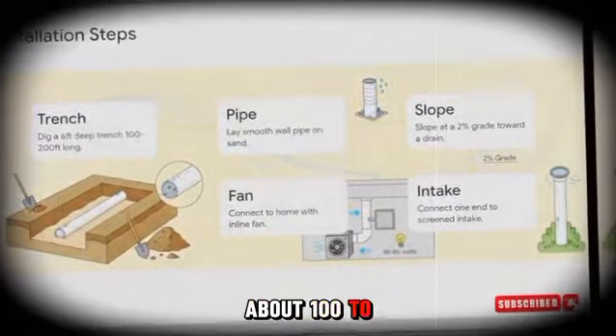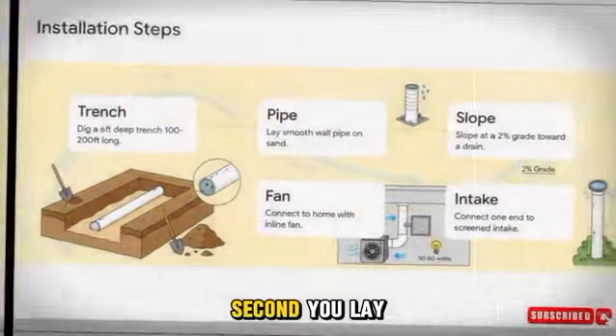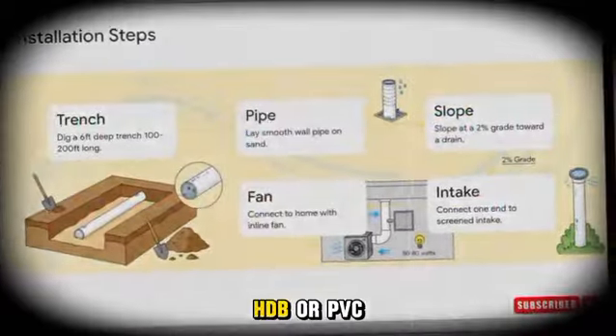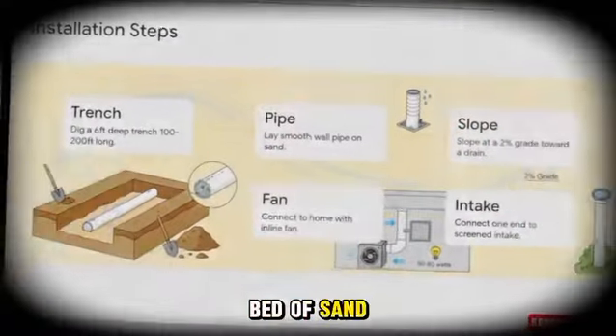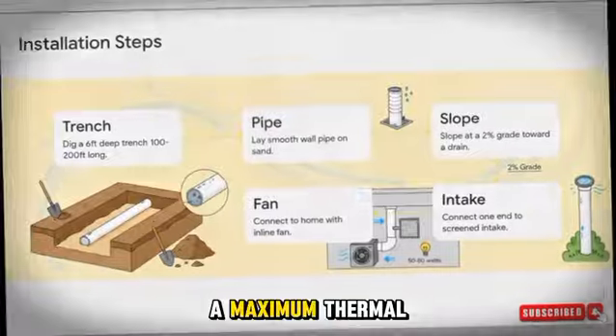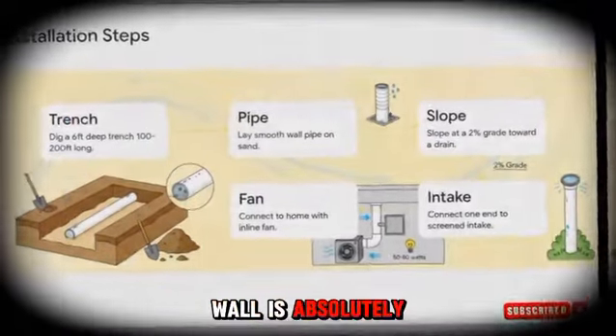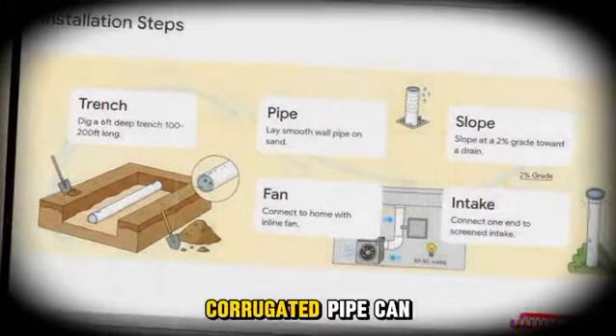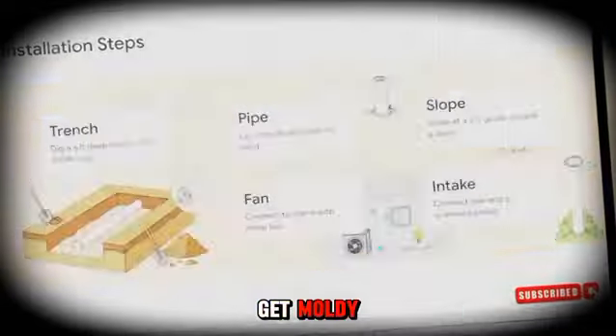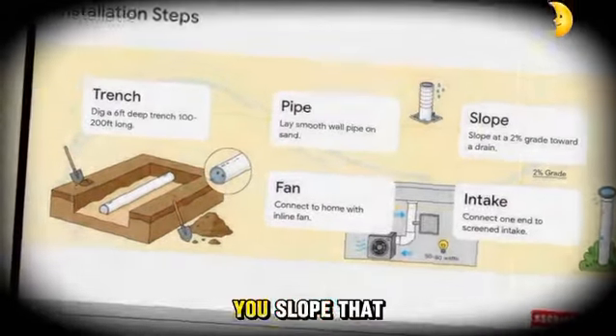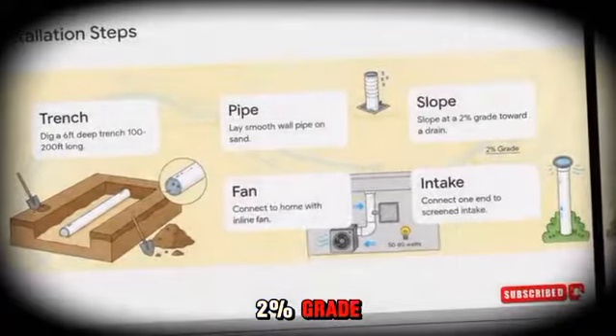First, you dig a trench 6 feet deep and about 100 to 200 feet long. Second, you lay down smooth-walled HDPE or PVC pipe on a bed of sand. The sand gives a maximum thermal contact, and the smooth wall is absolutely mandatory. Corrugated pipe can trap moisture and get moldy, so avoid that. Third, you slope that pipe at a 2% grade so any condensation just drains right out.